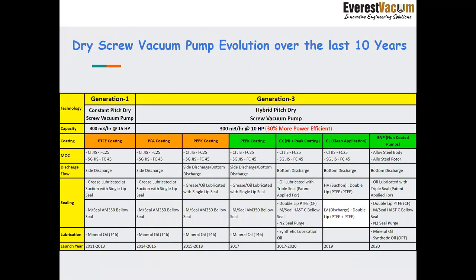Now coming to the dry screw vacuum pump, the evolution over the last 10 years, as you can see, we started from Gen 1 and now we are currently into Generation 3. Generation 1 dry screw vacuum pumps were constant pitch dry screw vacuum pumps. The size of the pitch was constant throughout from the suction to discharge, and for comparison purposes, we have taken one 300 meter cube per hour pump. It used to operate with a 15 horsepower motor. And coming to Generation 3, that connected power has come down to 10 HP. So it is altogether 30% more power efficient.